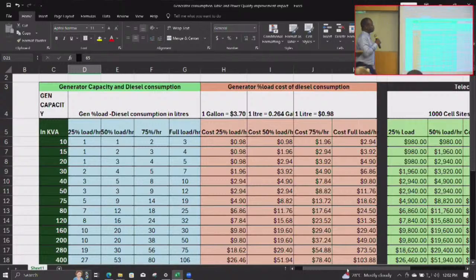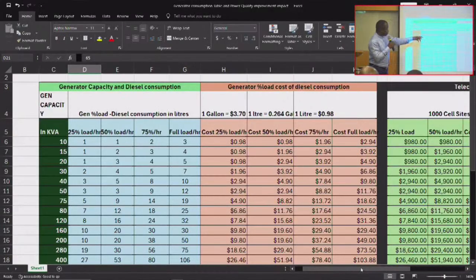Then we looked at the cost. At 25% load on 20 kVA, you're doing about 98 cents, approximately $1 per hour. If we scale up to 75% load on 20 kVA, we're talking about almost $4—that's the generator's consumption cost. George is here, and I'm glad he is—he's from Mantrack, a very seasoned engineer. So if this is way off from your experience, you can point it out. We can approximate it and see what we're actually spending.